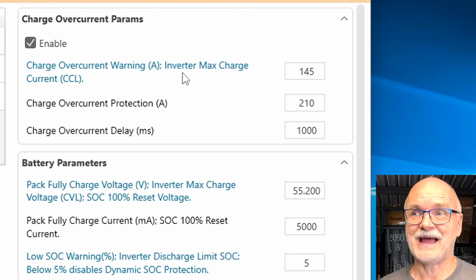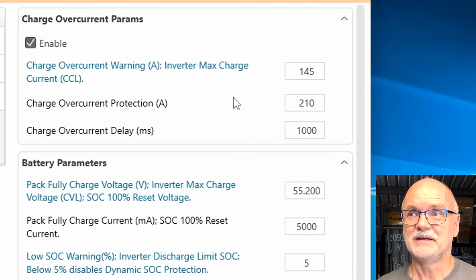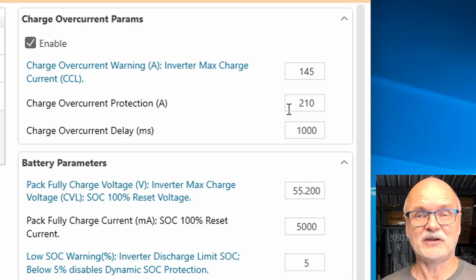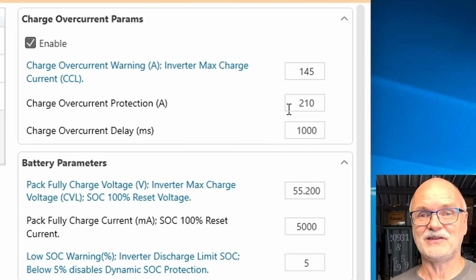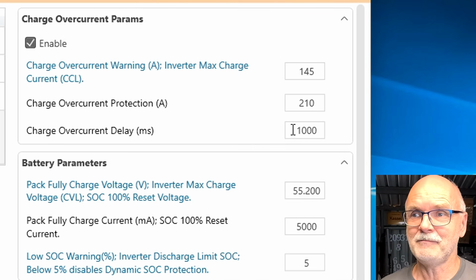This is at the same time your CCL, your inverter max charge current, 145 amps. The protection kicks in at 210 amps. So you can set your CCL lower than your protection. That is very, very good. Thank you. We've got a delay timer.